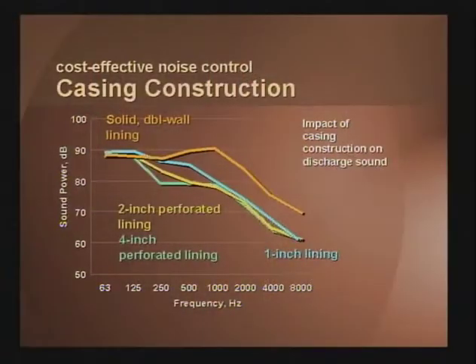This chart here shows the effect of insulation in a discharge plenum in a typical air handler. The yellow line at top, the orange line, shows a solid double wall lining. So you see that the sound going out of the unit is relatively high, basically unlined air handler. If you add 1 inch of fiberglass, you get a fairly good pull down above 500 hertz.